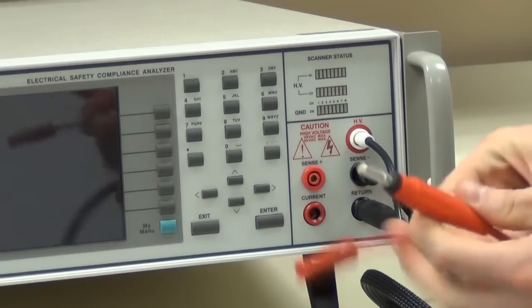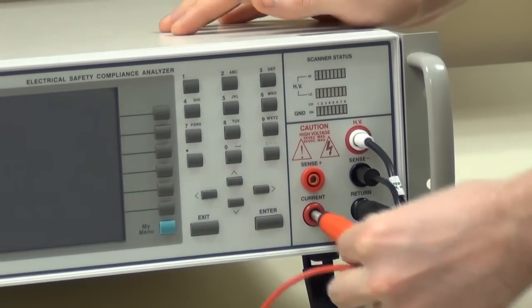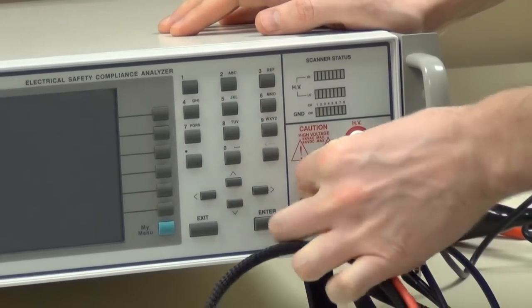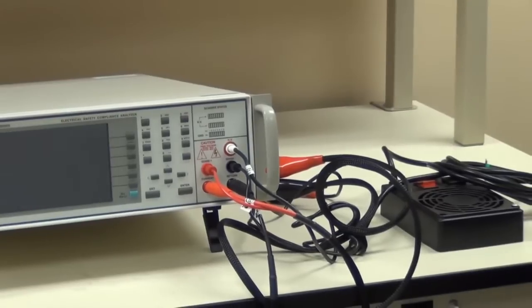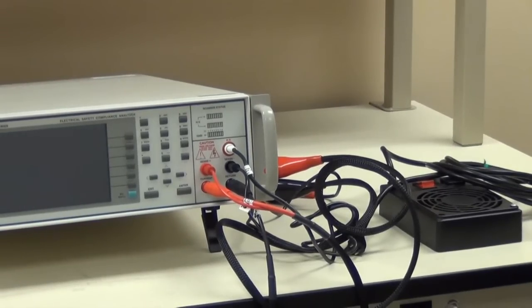If you're performing a ground bond or DC continuity test, connect the red high current lead into the current terminal and the red Kelvin lead into the Sense Plus jack. The clip at the other end will connect to a grounding point on the DUT.